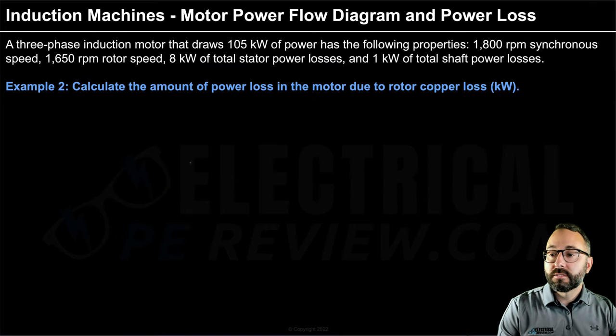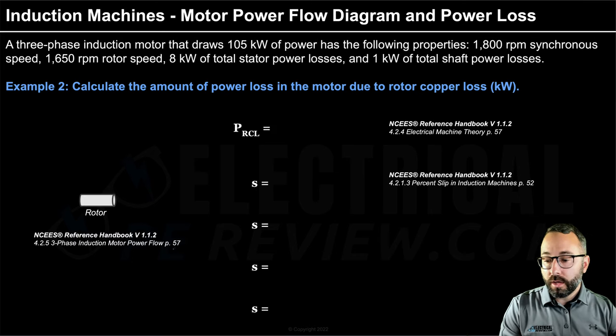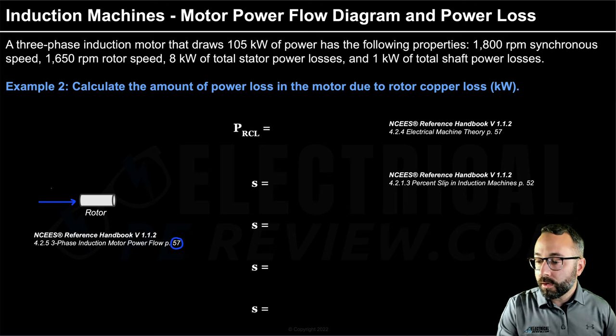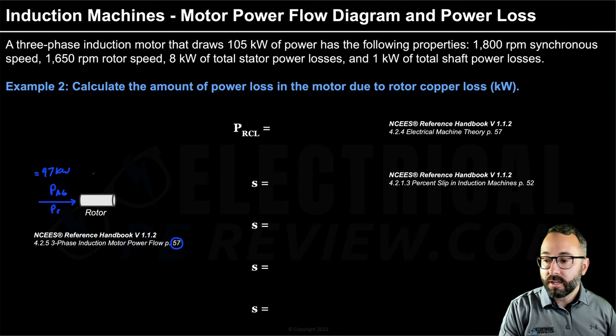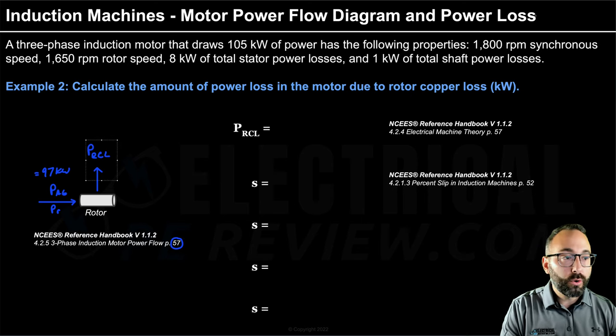Example two asks for the power loss due to rotor copper losses. The air gap power (rotor power) was 97 kilowatts. Similar to the stator, the rotor has copper losses only — no core losses. We can convert between air gap power and rotor copper losses using slip: rotor copper losses equal slip times air gap power. This formula is from page 57 of the reference handbook, section 4.2.4.